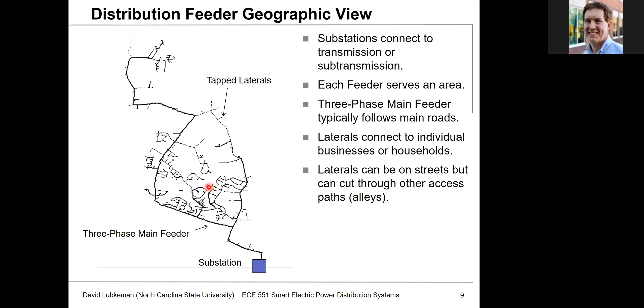For our overhead primary distribution, you'll see a lot of three-phase overhead. You might also see single phase and two-phase. When it comes to connecting to transformers, you may see the transformer mounted up on top of the pole, and the secondary is what goes to the customers.